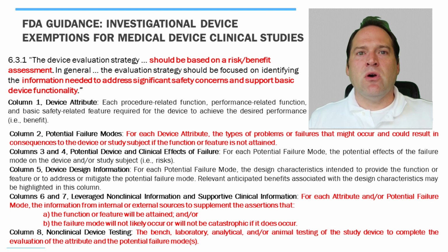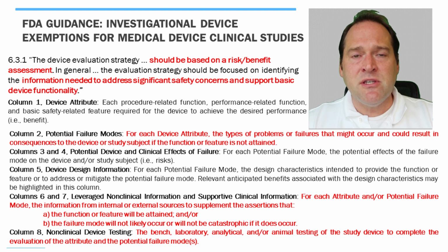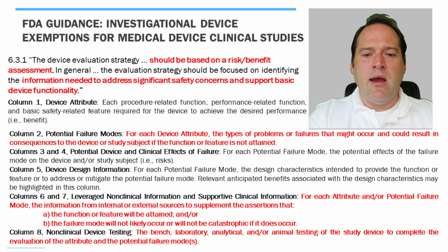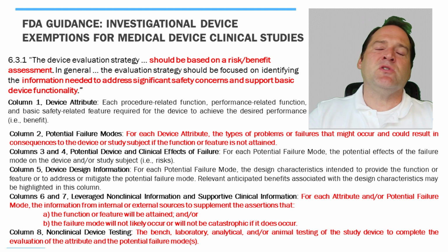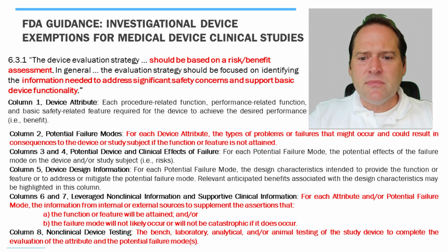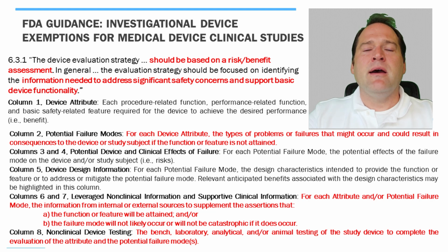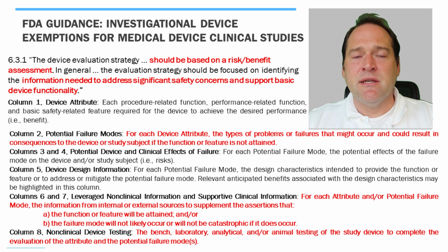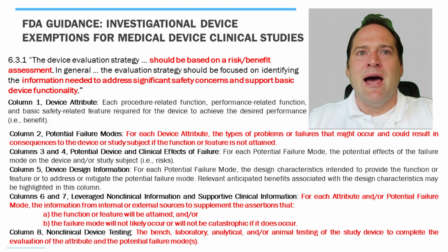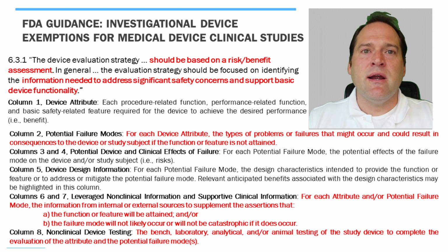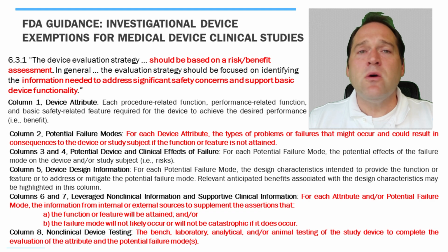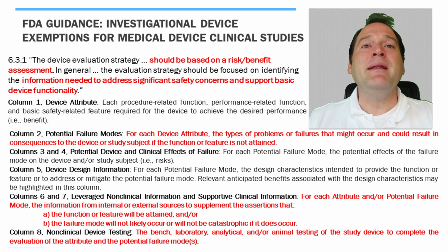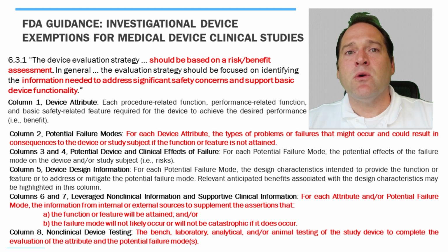This is often referred to, there are two different ways of looking at that. One is a failure modes and effects analysis, where you outline each individual component and you talk about how, if each thing fails, that can create a problem. And then there's a hazard analysis, which is more top-down, where at a 20,000 foot level you talk about all the potential risks that might occur and their severity, and then you work backwards from that. Now, your non-clinical device testing is really to mitigate these risks. You outline the bench, laboratory, analytical, and/or animal testing of the study device to complete the evaluation of each potential failure mode. And ideally, you're trying to get all probabilities of a risk occurring to be low and the consequences of that risk occurring to be low. That's not always possible, and many IDEs get approved even though there's maybe something with medium risk and medium severity if it does occur, but the benefits of taking that risk outweigh the potential consequences.